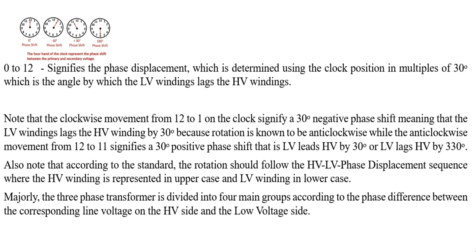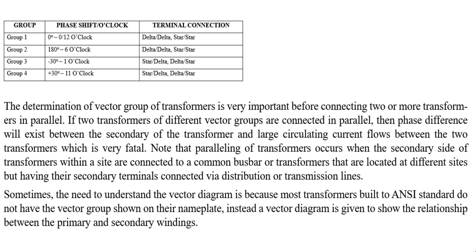The phase of a transformer is divided into four main groups. Group one is zero degrees — the clock sign is on 12 o'clock, and the only connections possible are delta-delta or star-star. Group two is 180 degrees, at 6 o'clock, which can also have delta-delta or star-star connection. Group three is minus 30 degrees, or 1 o'clock — it has moved clockwise from 12 to 1 — and can be either star-delta or delta-star connection. Group four is plus 30 degrees, or 11 o'clock, moving anti-clockwise from 12 to 11, and can also be star-delta or delta-star connection.